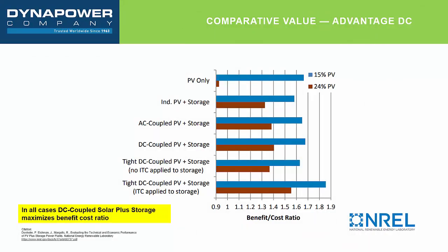So those benefits are perhaps intuitively clear, but it was actually a team at NREL that last year put numbers on the comparative values for the base case of PV only versus AC coupled and DC coupled PV plus storage. This analysis considered both cost and revenue sides. And in the final analysis, the DC coupled system demonstrates the highest benefit ratio of all possible configurations that were looked at. What's interesting is that the analysis, of course, takes into account the fact that you cannot charge the batteries from the grid because they're sitting behind a unidirectional PV inverter.